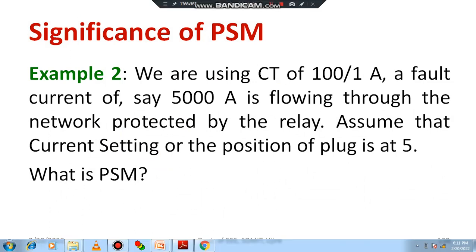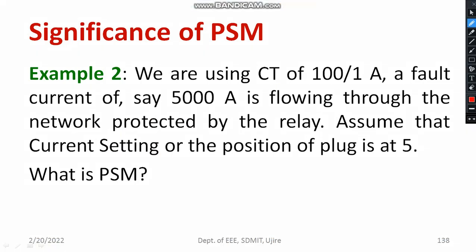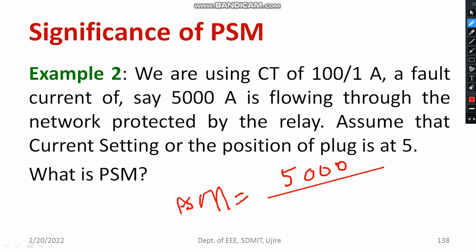Can you work out this second problem? PSM is nothing but fault current divided by (PS × CT ratio). Fault current is 5000, PS is 5, and CT ratio is 100 by 1, which is simply 100. So PSM equals 5000 divided by (5 × 100), which gives PSM equal to 10.